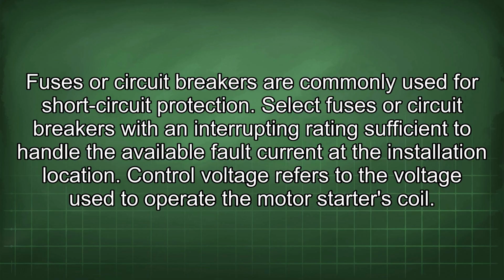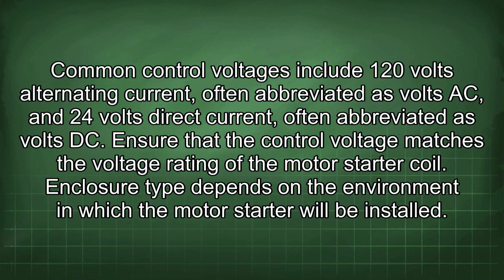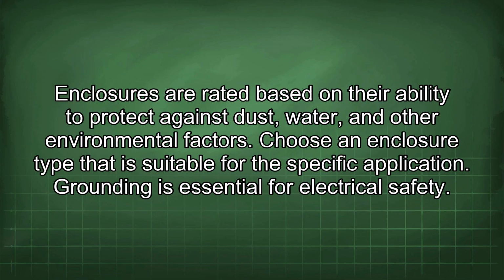Control voltage refers to the voltage used to operate the motor starter's coil. Common control voltages include 120 volts alternating current, often abbreviated as volts AC, and 24 volts direct current, often abbreviated as volts DC. Ensure that the control voltage matches the voltage rating of the motor starter coil. Enclosure type depends on the environment in which the motor starter will be installed. Enclosures are rated based on their ability to protect against dust, water, and other environmental factors. Choose an enclosure type that is suitable for the specific application.